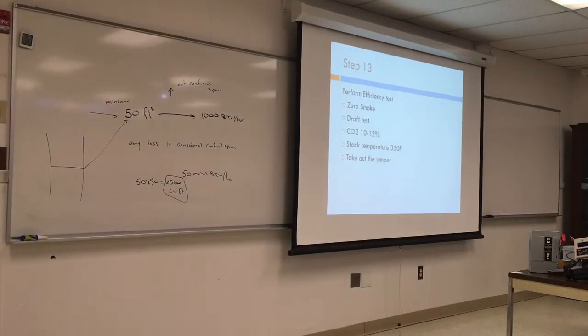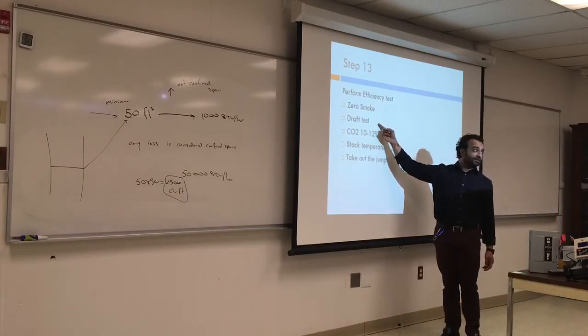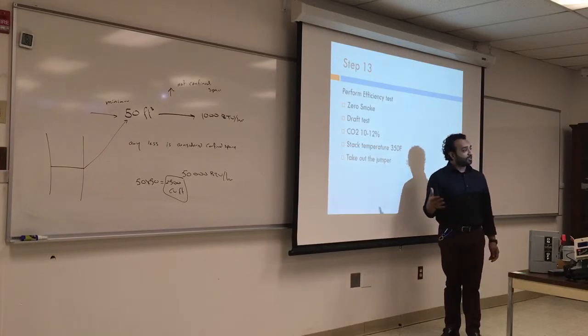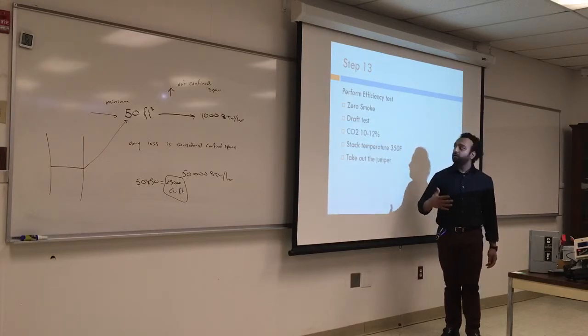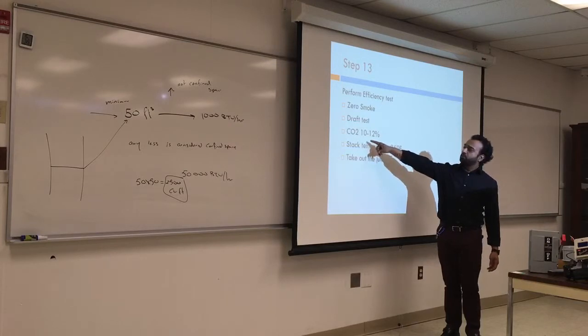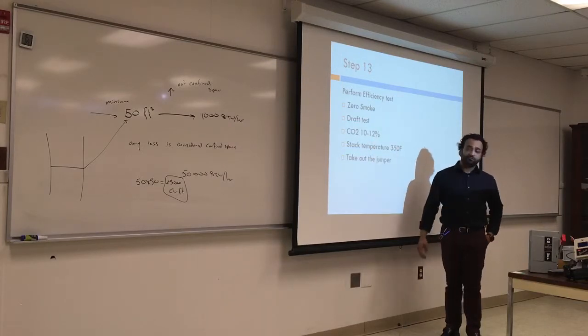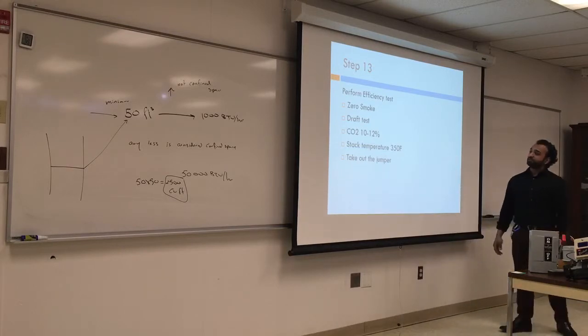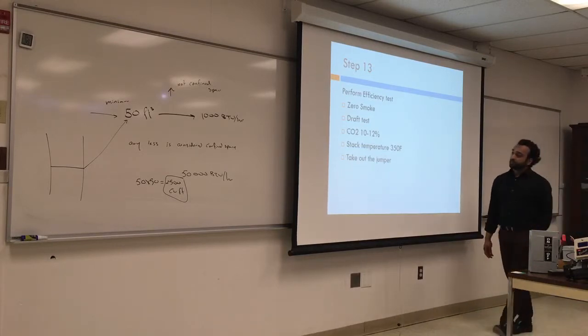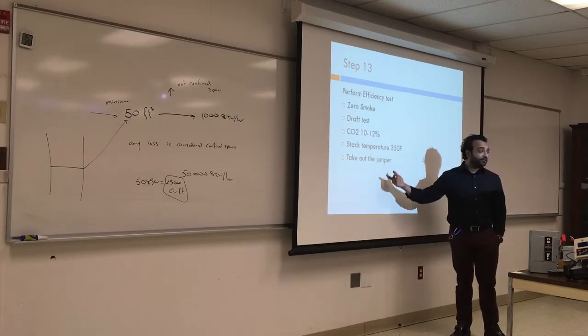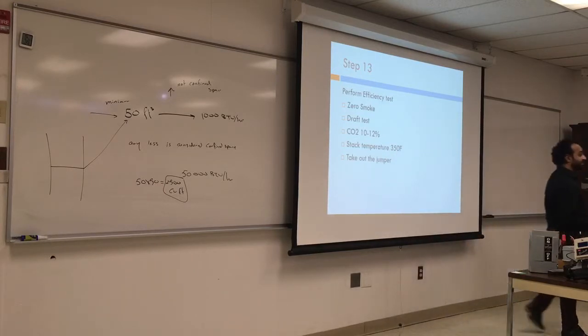Step 13, do an efficiency test. Before you do an efficiency test, you should leave the burner off at least 10 to 15 minutes to burn any excess gas existing in the chamber and to stabilize the temperature. We should aim for zero smoke. We'll do a draft test. A draft test is basically the vacuum pressure, the airflow in the chamber. CO2 should be between 10 and 12%. Stack temperature should be around 350. And once it's running, take out the jumper. Don't leave it there because otherwise the system will be on the whole time.